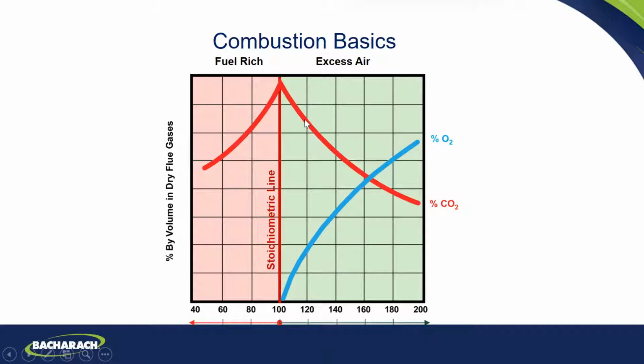So I could be, after work, drinking a Frosty with some other boiler technicians, and I could say I like to set my boiler at a certain percent CO2. Another one says, well, I like to do this percent oxygen right here. Another one says, well, I like to do this at 100% excess air. You all said the same thing. So with a combustion analyzer, we measure oxygen, we calculate CO2, we calculate excess air, and then we calculate efficiency.